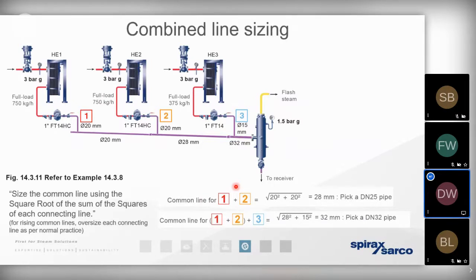And once again, we can size the group condensate lines correctly by referring to that little app that we've spoken about. So hopefully you can appreciate that steam traps need a motive pressure in the steam to push the condensate across the trap to a lower pressure so the condensate can move. And hopefully you can appreciate that as mechanical devices, they are susceptible to failure. That's typically when they're exposed to a poor condition of steam or condensate, or when they've been incorrectly sized, incorrectly installed, or incorrectly selected. So steam traps will typically fail in one of two conditions, open or closed.